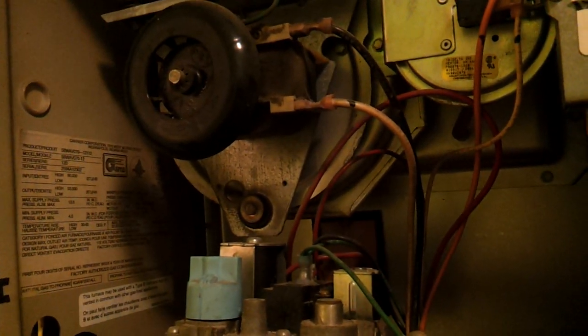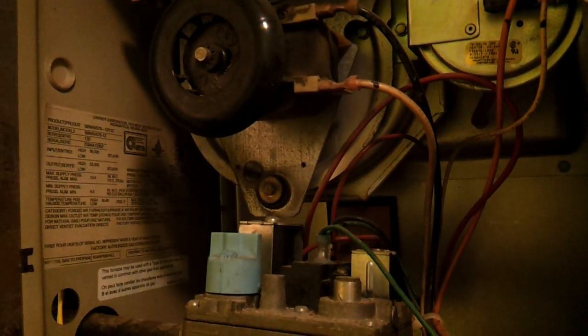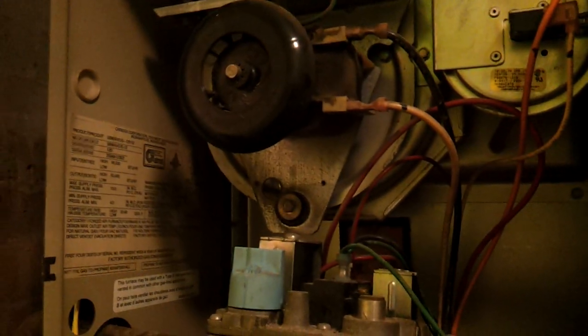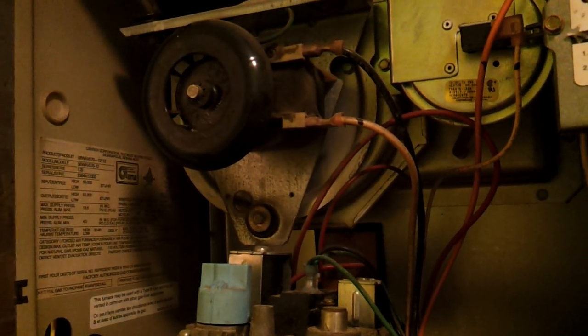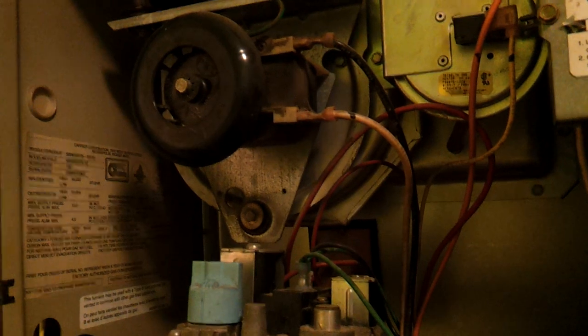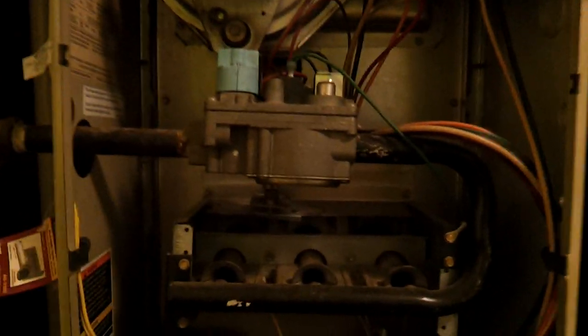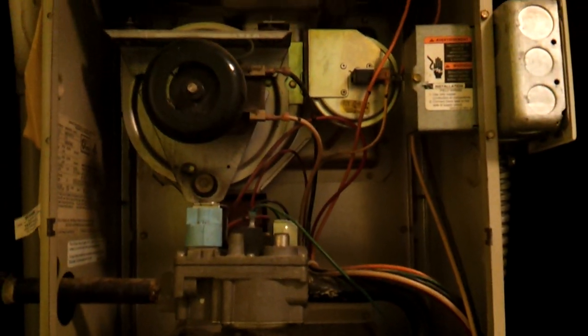It is a 58 WAV 070-12 gas furnace. It is the 120 series. And it's 66,000 BTUs in, about 53,000 BTUs out. It's a pretty much standard 3-burner, 80% induced draft furnace. We've got a couple of things in here.